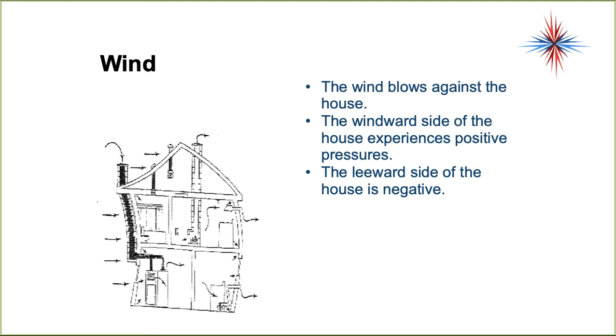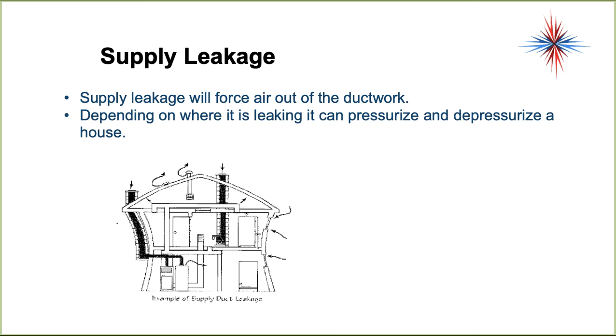Wind blows against the house: the windward side experiences positive pressures and the leeward side experiences negative pressure. Supply duct leakage is something many people don't think about. If a supply duct — the air going to the rooms from the furnace or air handler — is leaking in an unconditioned space like an attic, it forces air out of the ductwork. This can pressurize or depressurize a house depending on where it's leaking. A supply duct leaking in an attic will pull all the air out of the house and cause a negative pressure situation.